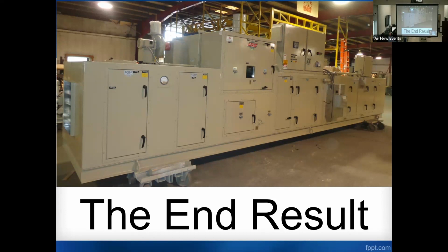You can side stream it with a makeup air unit or a rooftop unit. When you're doing your pre and post cool and it's DX, that's a little bit of a hairy combination sometimes. So we use two separate condensing units, a pre-cool separate DX and a post-cool separate DX, because the airflow is so low. We use hot gas bypass, electronic expansion valves, and liquid injection, all to keep the condensing units running.